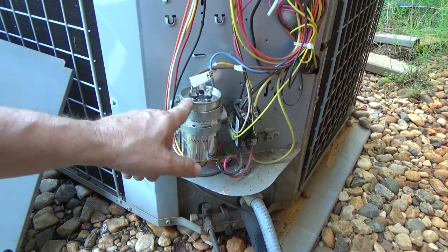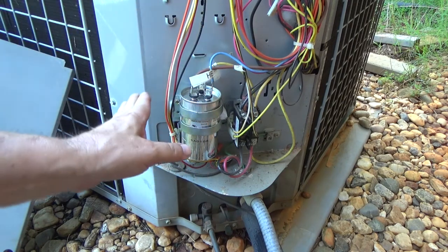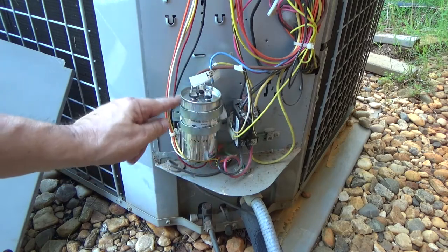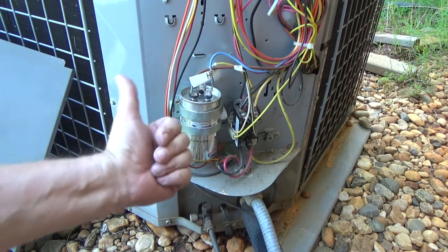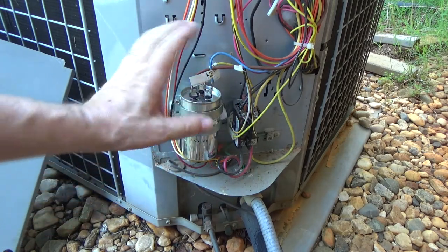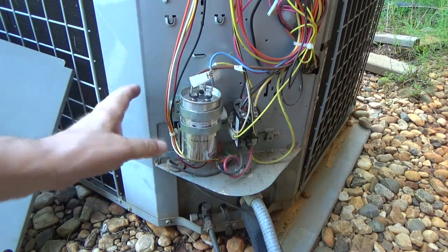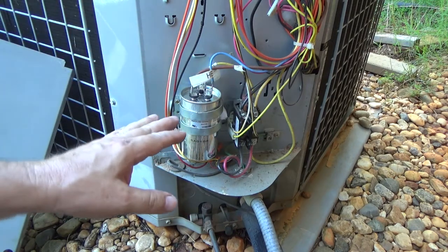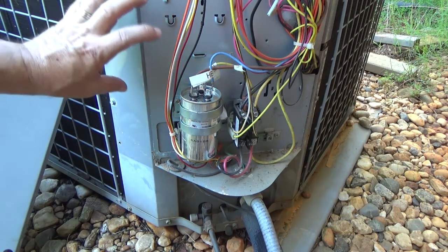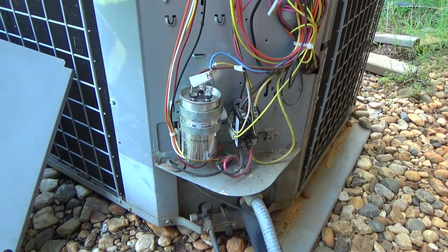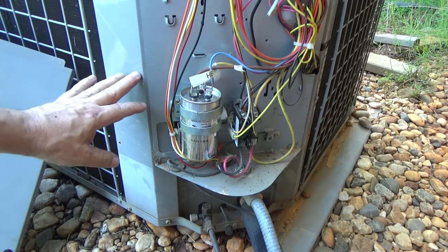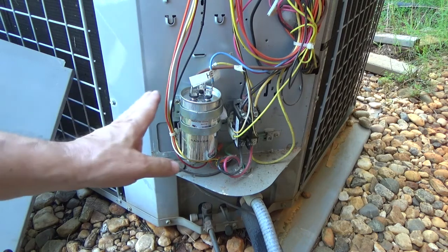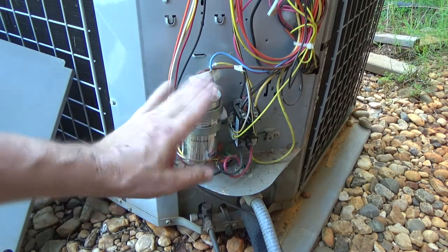But anyway, this will get rusty, and if it bubbles up, I mean the whole thing, these guys are going to be all tilted to the side. This is a big bubble in there. If it's running, it's almost gone. If it's not running, you hear it humming, the fan's not spinning, the compressor's making a hum noise, and you see that big huge bubble in there.